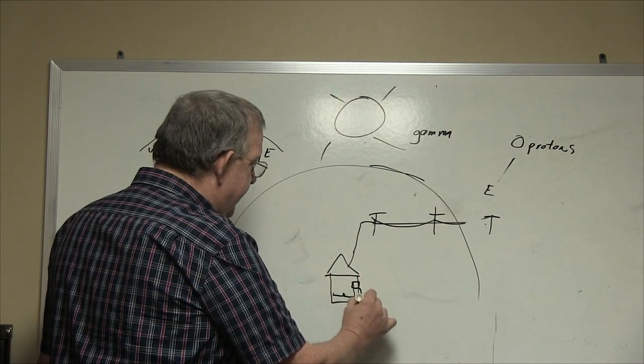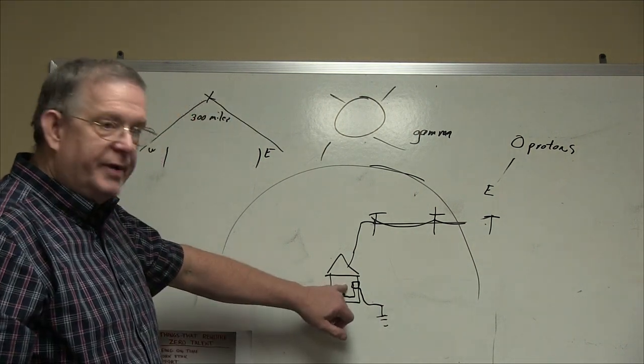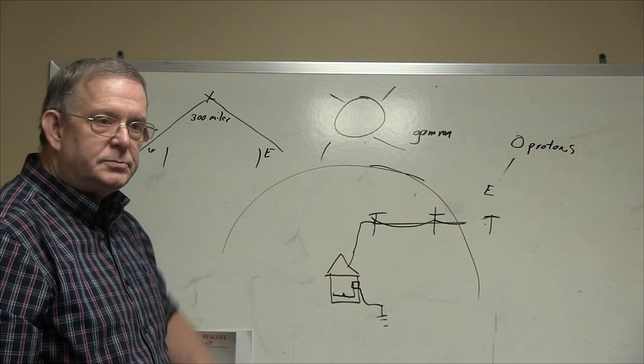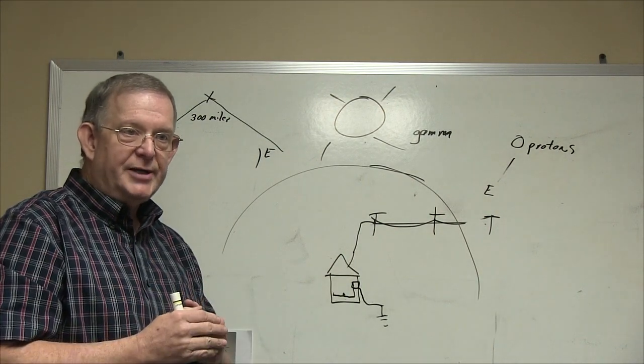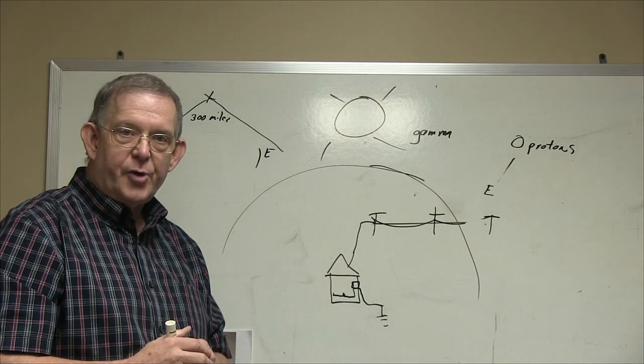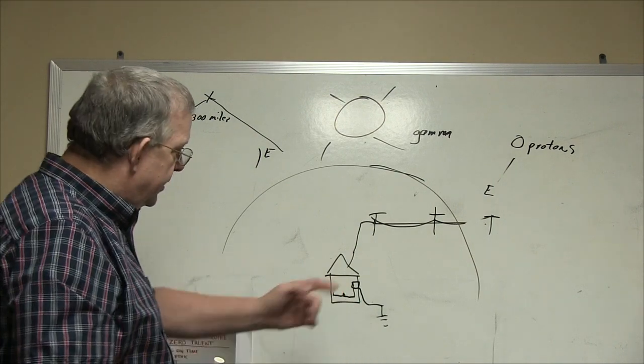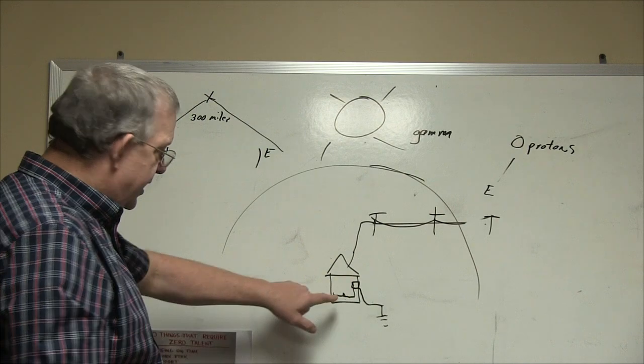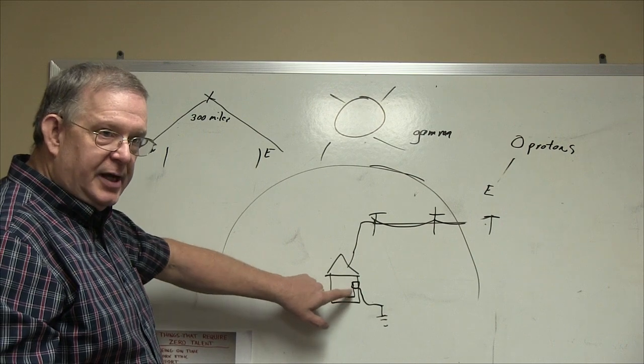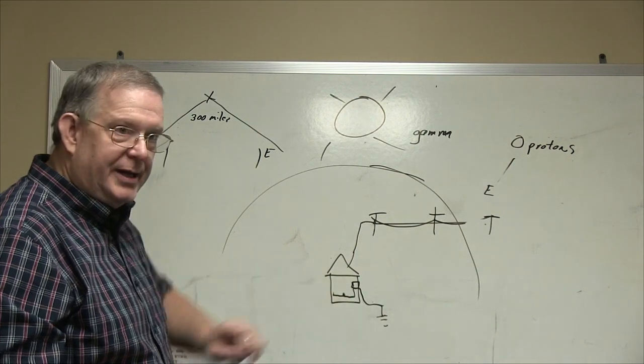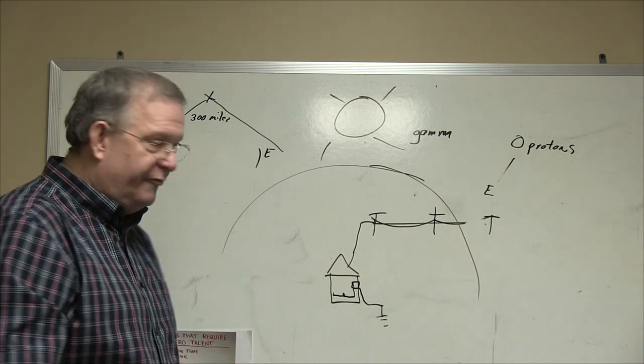With our device, we're taking it and looking at it and taking it to ground when it sees any kind of fluctuation above the threshold at the electrical panel. And that's why when we see any kind of spike above the threshold that is set forward, we take everything to ground and conductor to conductor so the spike doesn't reach the person's equipment. Now again, the wire between our unit and where the equipment is in the house is still part of an antenna, but we are still shunting it at the panel. So the impact to the piece of equipment is very negligible for the normal shielding.